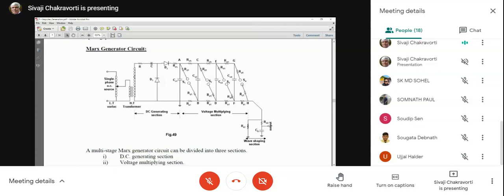are immediately in series. So the voltage across S2 becomes 2V, and then it will automatically fire because of the very high voltage. Then the voltage across S3 will become 3V. It will fire. Voltage across S4 will become 4V. It will fire.